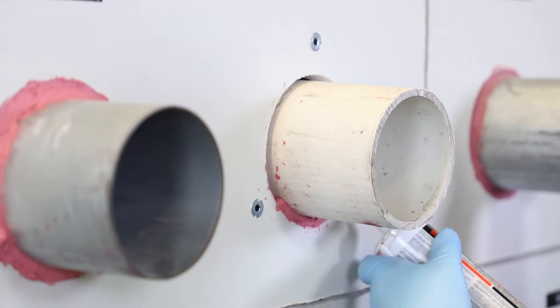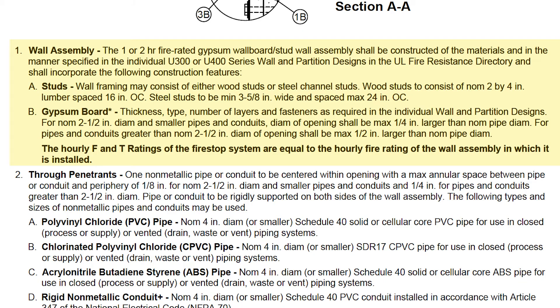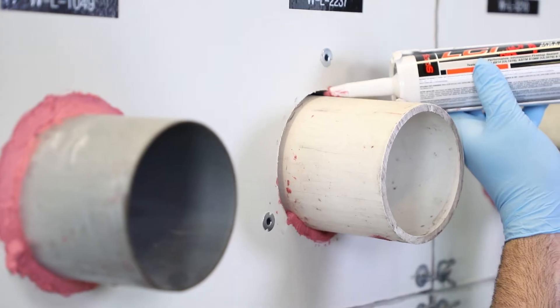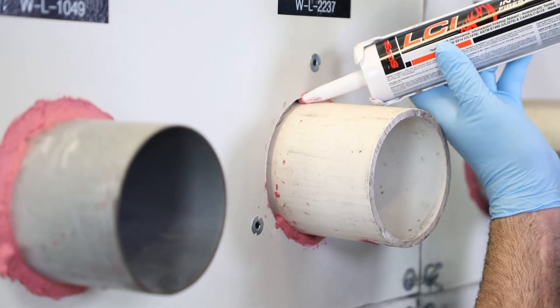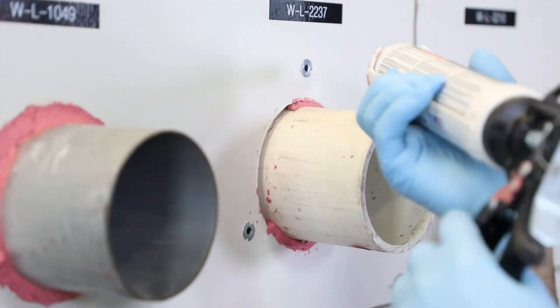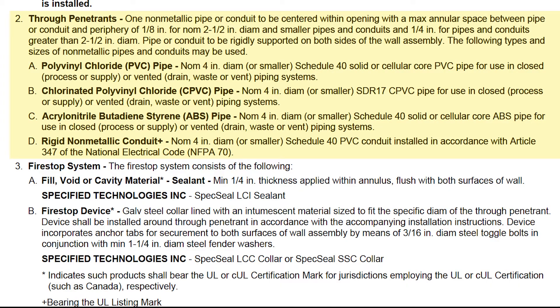Starting from the top, we'll read this through. WL-2237 is good for a one or two hour wall. Our through-penetrants can be anything from four inch PVC to four inch CPVC, four inch ABS.